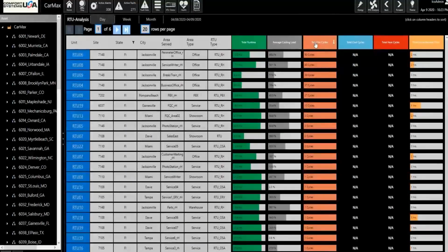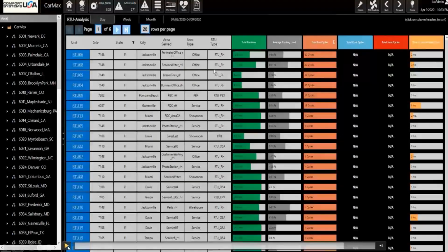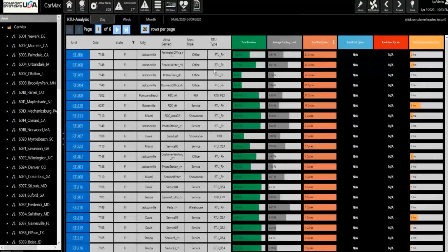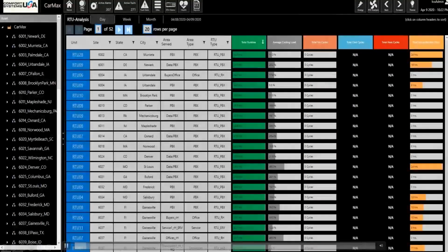In this case, I'm looking at fan cycles. Obviously when I have 60, 70, 60, 40 cycles occurring, I'm tearing that equipment apart. Somebody probably has the deadband set too low in the thermostat, or the thermostat is too close to the exhaust output. But all of this data is being modeled in memory at very high speed so that I can sort through it and have it create insight for me.